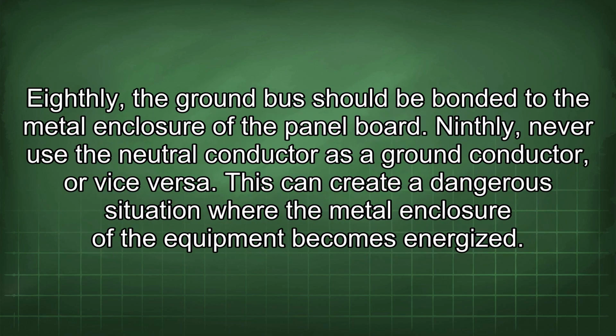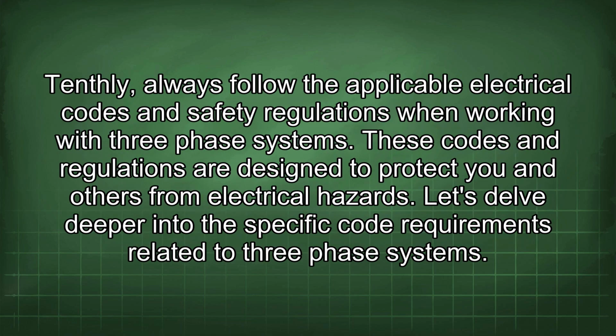Eighthly, the ground bus should be bonded to the metal enclosure of the panel board. Ninthly, never use the neutral conductor as a ground conductor, or vice versa. This can create a dangerous situation where the metal enclosure of the equipment becomes energized. Tenthly, always follow the applicable electrical codes and safety regulations when working with three-phase systems.